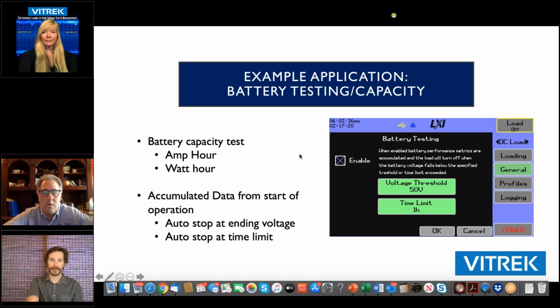Typically, if you're using this battery capacity mode, you're going to set a time limit. If you were doing a capacity test, let's say you wanted to verify that within an hour you're going to get a certain amount, you can set a hard time limit. You can also set a voltage cutoff limit. Most batteries, at least lithiums with a battery management system, have a cutoff, and you'd want to set your test limit right at that or slightly above it, so it doesn't shut off first.